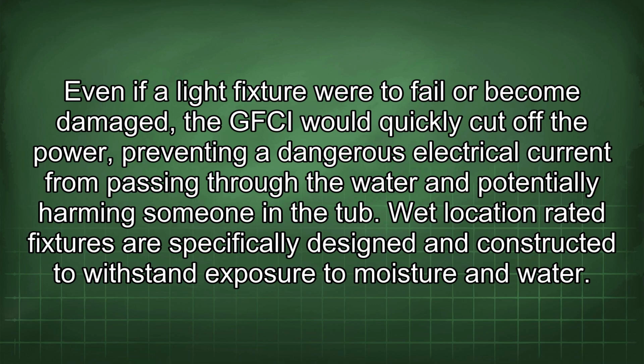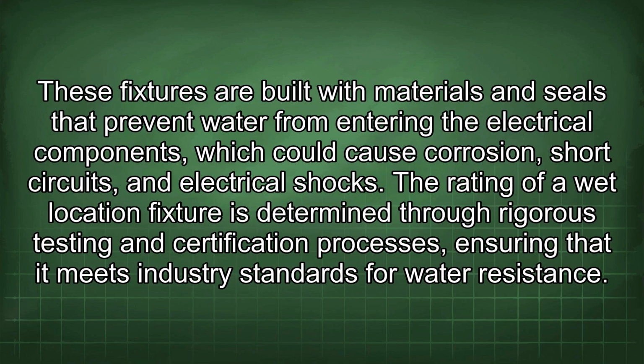Wet location rated fixtures are specifically designed and constructed to withstand exposure to moisture and water. These fixtures are built with materials and seals that prevent water from entering the electrical components, which could cause corrosion, short circuits, and electrical shocks. The rating of a wet location fixture is determined through rigorous testing and certification processes, ensuring that it meets industry standards for water resistance.